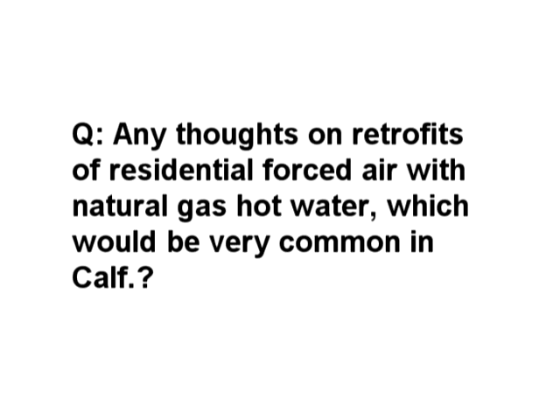Retrofits of residential forced air systems with natural gas hot water heaters. I would say that the real retrofit market that's very attractive here is propane, where people are suffering under the utility costs associated with that, and where you'd be going in and taking out the forced air unit, maybe using the same ducting, and putting in a variable speed air handler with hot and chilled water. That would be a very good choice, unless you're in, of course, a utility area where you have more than 18 cents a kilowatt hour. Then that is a very good retrofit market. There are many parts of the country where the retrofit market is going to be instantaneous against natural gas. Here, you have to pick your spots.